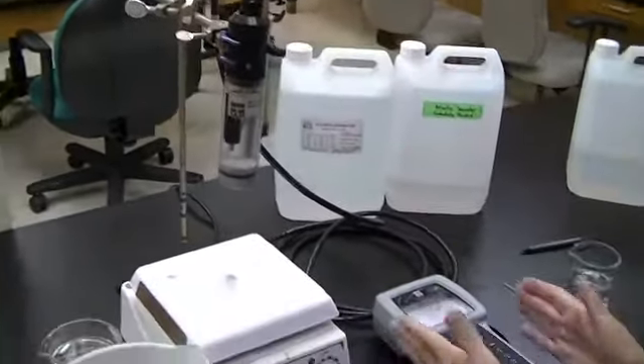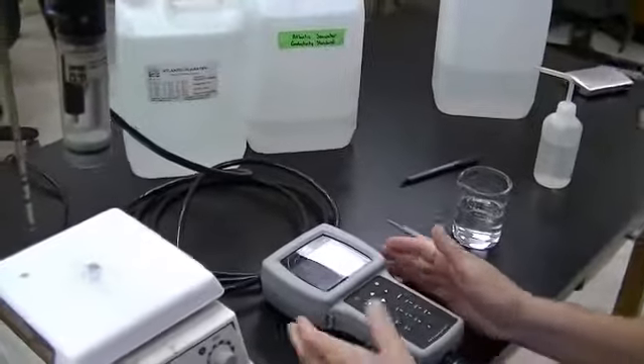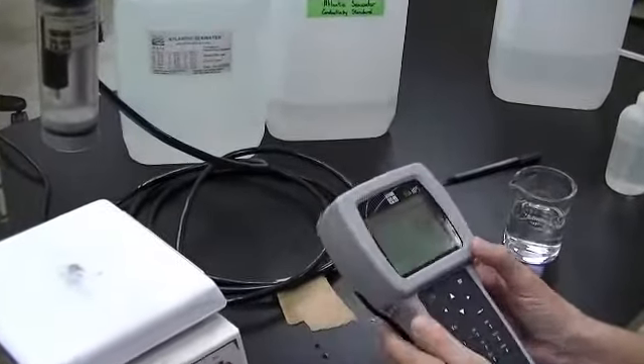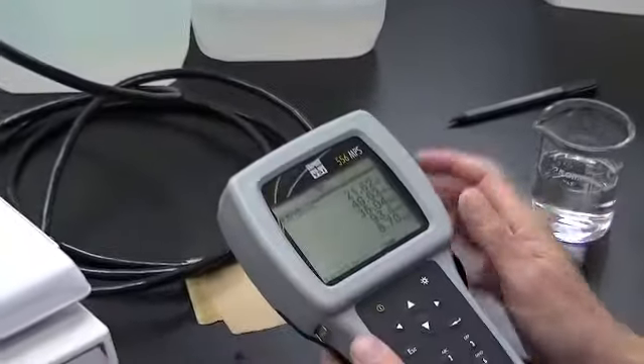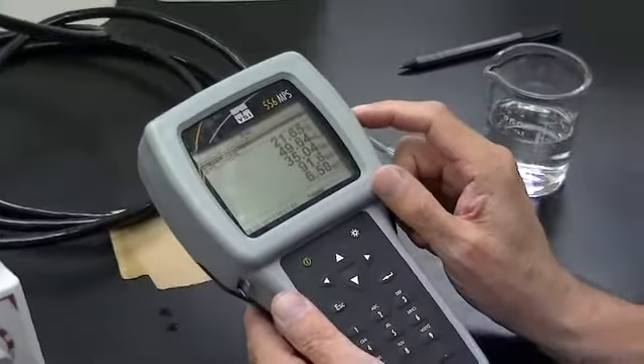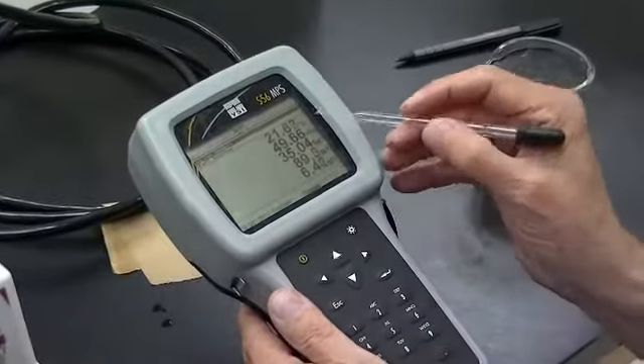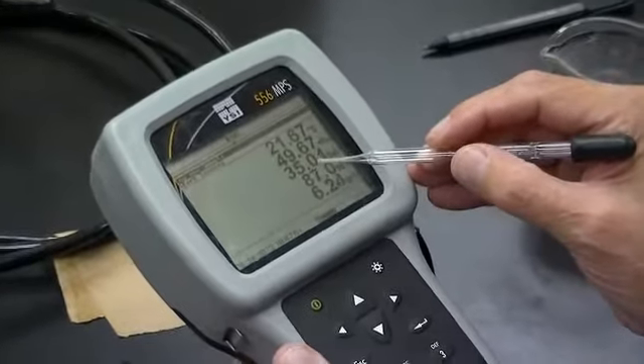And now we're ready to focus on the instrument. Here we see the instrument says 49.63, and the number is changing. That is millisiemens per centimeter. That number right there, the second one, is the conductivity. And then the third one is salinity.